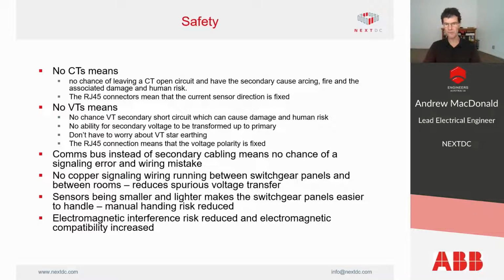The sensors are much smaller and lighter than conventional CTs and VTs, which makes the switchgear panels easier to handle, so the manual handling risk for them is reduced. And using optic fibre means the electromagnetic interference risk is reduced and the electromagnetic compatibility is increased.